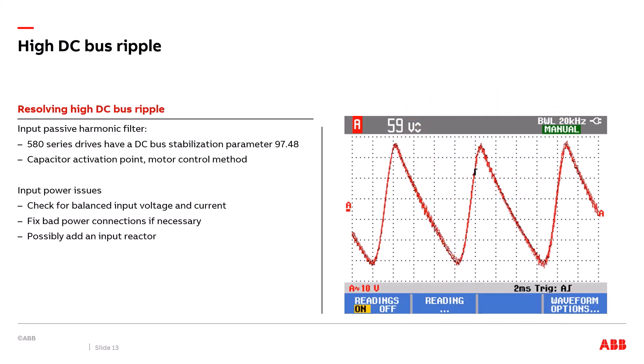Now that we know how to look at the DC bus on a scope what happens if we see a high voltage peak to peak ripple on the DC bus and we have the drive tripping out on faults. How do we resolve the problem? Well it depends on what's causing the problem. The most common cause of a high voltage DC bus ripple is because an input harmonic passive filter has been attached to the front of the drive to reduce input harmonics on the electrical system. That passive harmonic filter's capacitors usually will start to resonate with the drive's DC bus capacitors. So how do we fix that? On the ABB ACH 580 series drive we actually have a parameter called DC bus stabilization which is parameter 97.48 that can be adjusted to help resolve the problem. Other solutions are to adjust that capacitor activation point or when the contactor for the capacitor and the filter pulls in or also the motor control method maybe trying a vector control method instead of scalar.